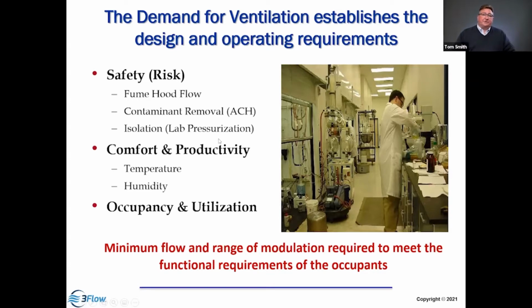If there was a spill or some type of escape in the space, we don't want it to migrate to non-lab spaces, so pressurization becomes very important. We also have to simultaneously provide comfort conditions, so our temperature and humidity. And then, if we want to save energy, we want to modulate the systems based on occupancy and the use of the devices. So if they're not using a hood and they close the sash, we want the flow to go down. If they're not in the labs, we want to employ occupancy controls and reduce the flow.